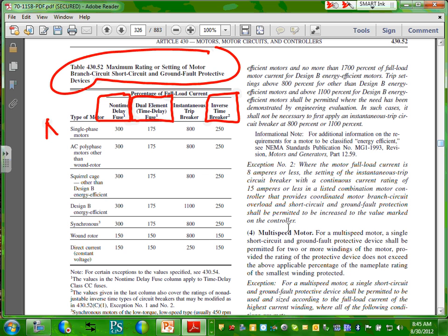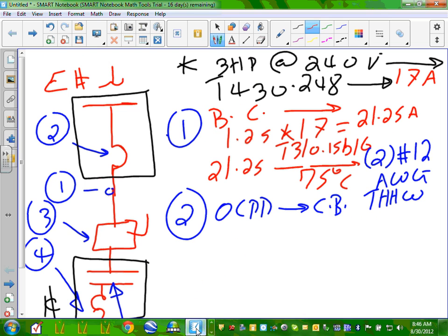Everybody knows single phase is right here, so I'm looking at single phase. If I'm using this type, what's my multiplier? 250. And if you read through here, it will tell you if you don't land on a standard circuit breaker, you go up. Can I have thumbs up that everybody knows how to use this table? If I use a fuse, it will be 300. If I use a non-time delay fuse, 300. If I use a dual element, 175. If I use an instantaneous trip, 800. So we're going to be using an inverse time circuit breaker. Okay, we got that. Let's go back, so we know where we got that one from. What was the table again? Table 430.52.